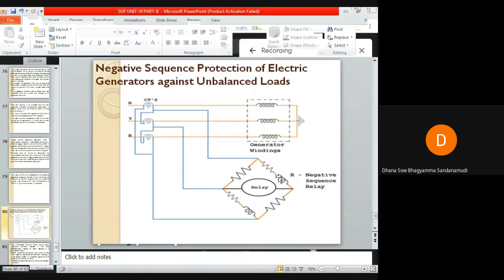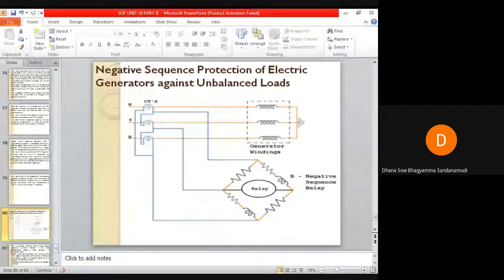When this negative sequence relay senses the temperature of the rotor, if that temperature reaches the preset value, then this relay will operate and disconnect the unhealthy section from the healthy section. It will give a signal to the circuit breaker and the circuit breaker will open.